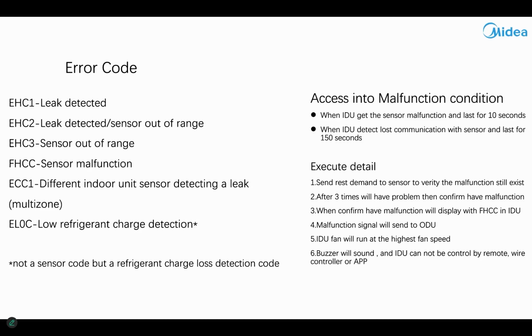There's a buzzer on the indoor unit that sounds. Louvers open, that's on ductless. There are some other things in there. FHCC is a sensor malfunction, triggered if the indoor unit can't talk to the sensor for at least 10 seconds, and if it loses communication and that lasts 2.5 minutes, it will go into an FHCC. FHCC means you either have a bad sensor or a bad connection somewhere. We've already eliminated the bad connection. I'll show you that: there's one connector in that box that is just a 2-wire connector. That's the A2L sensor, and it is a waterproof, moisture-proof connection.